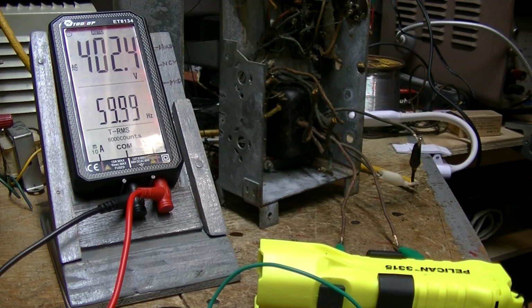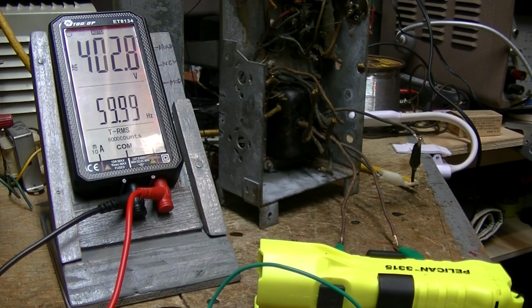We're not drawing any current. We shouldn't be -- that would mean we had a shorted winding on the primary or secondary if we had a current draw. An unloaded transformer will draw some current on initial startup, when you first apply power, but not continuously, unless you have a load on it or a shorted winding. That's 70 volts.